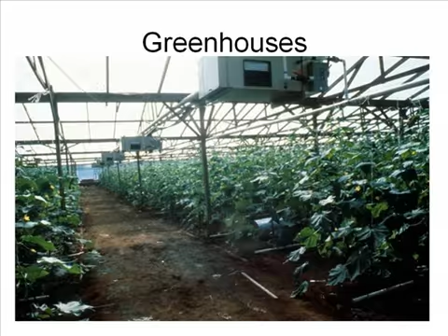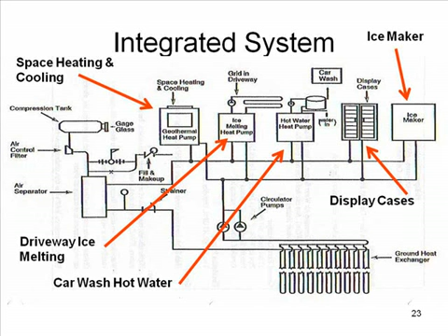One of the real advantages of this technology is the ability to integrate loads. For instance, if you have a car wash and an ice maker at a service station, the ice maker rejects a lot of heat, and that heat can be used in the car wash. If you want to control the water temperature in the car wash, you can put a heat pump on there and raise it to the desired temperature. The same ground heat exchanger can then supply the space heating and cooling system. The display cases that cool beverages and sandwiches also reject heat, and you can combine all these loads.